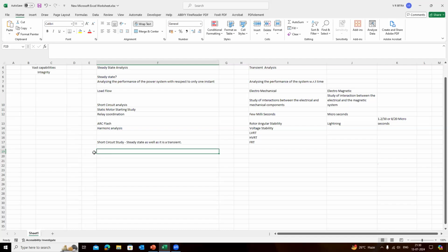If you are using the standard IEC 60909, that is a steady state short circuit. Whereas if you are using IEC 61363, then it is a transient short circuit. This is because IEC 60909 is applicable for short circuit calculation in low voltage or medium voltage 3-phase AC systems, and high voltage AC 3-phase AC systems operating at 50 Hz or 60 Hz. This standard predominantly talks about performing short circuit studies under steady state conditions. IEC 61363 is for transient short circuit.